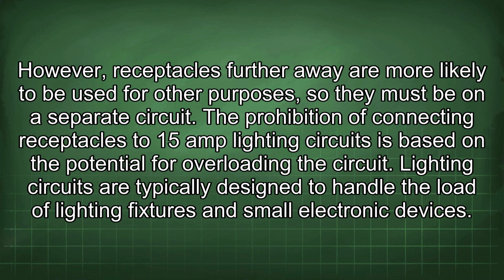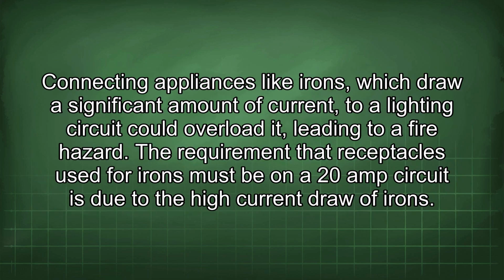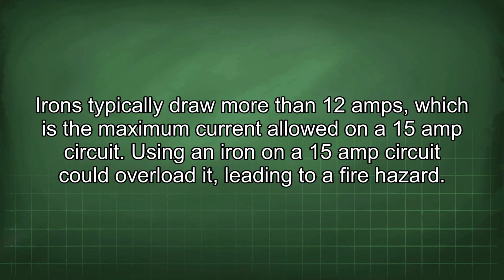Lighting circuits are typically designed to handle the load of lighting fixtures and small electronic devices. Connecting appliances like irons, which draw a significant amount of current, to a lighting circuit could overload it, leading to a fire hazard. The requirement that receptacles used for irons must be on a 20-amp circuit is due to the high current draw of irons. Irons typically draw more than 12 amps, which is the maximum current allowed on a 15-amp circuit. Using an iron on a 15-amp circuit could overload it, leading to a fire hazard.